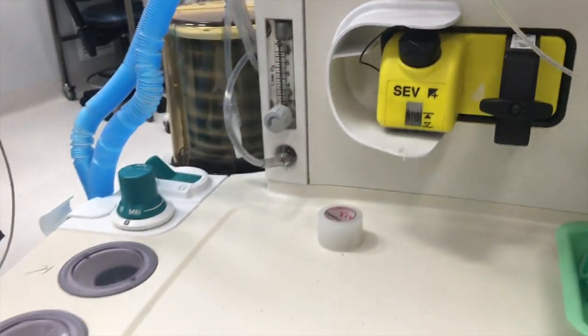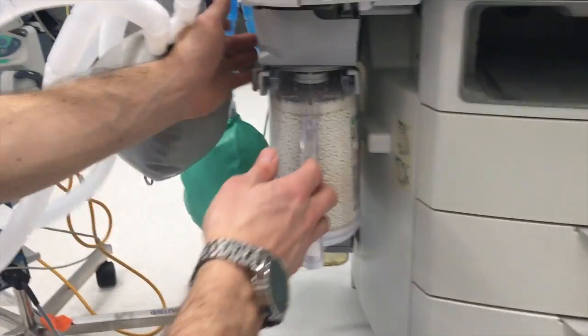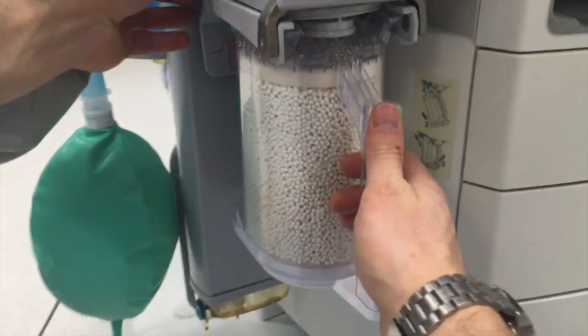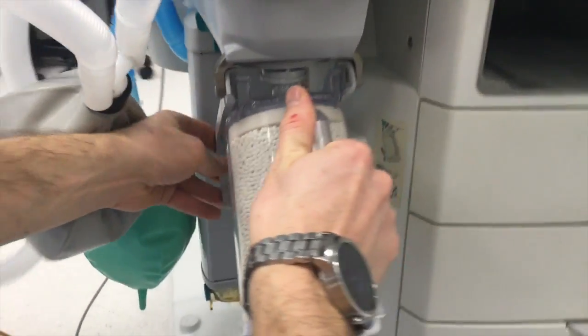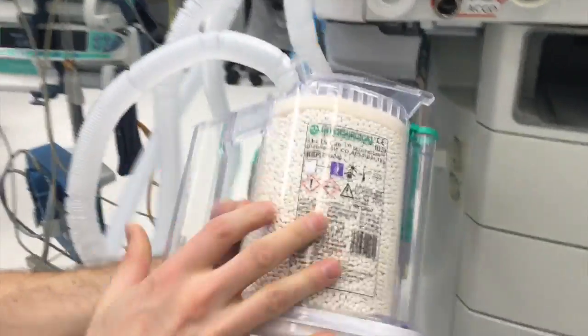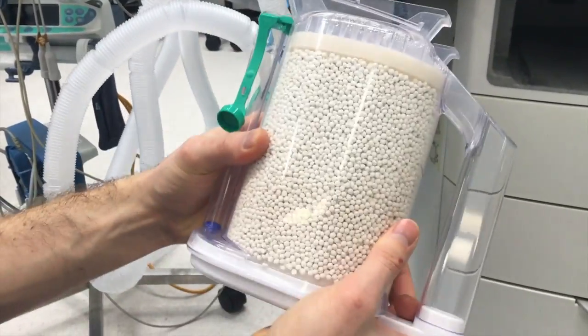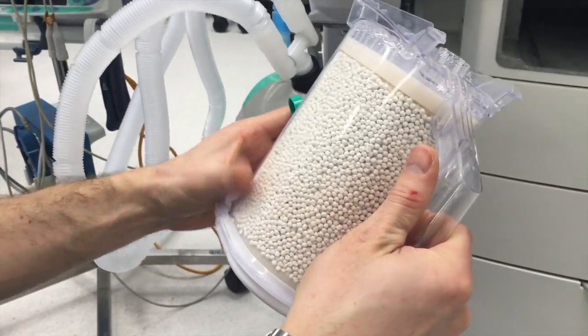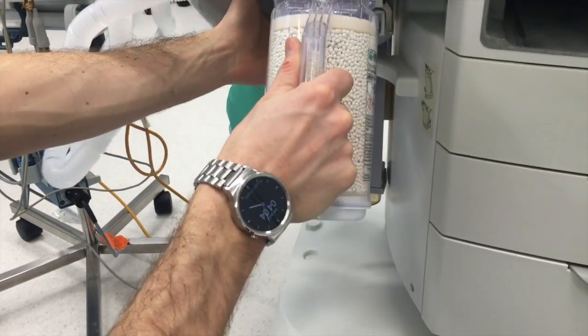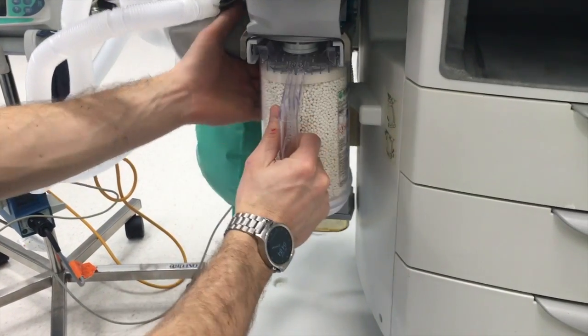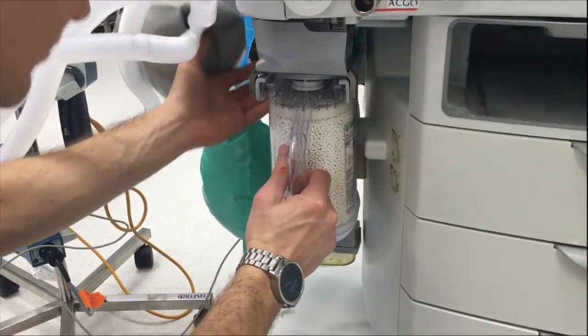It's also important not to forget the soda lime. This is used to absorb all the carbon dioxide in the circuit, but only works if it is fresh. Soda lime turns purple when it needs to be replaced due to an added indicator dye. Make sure it is correctly reinserted because even small gaps can cause a leak.